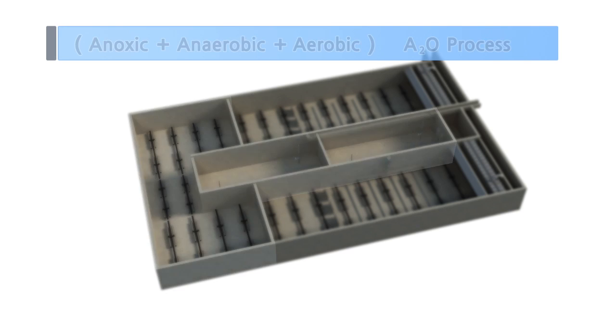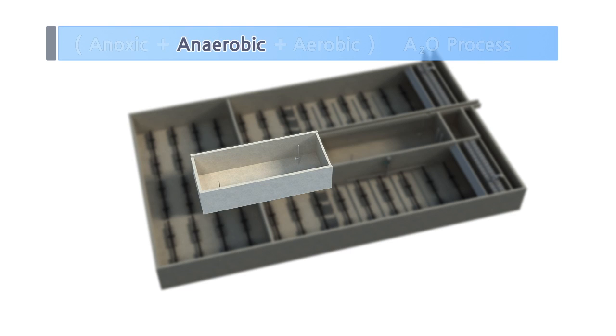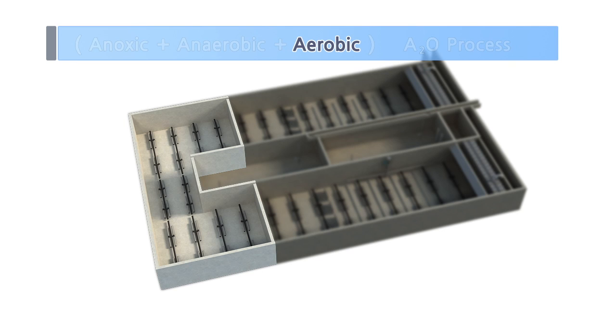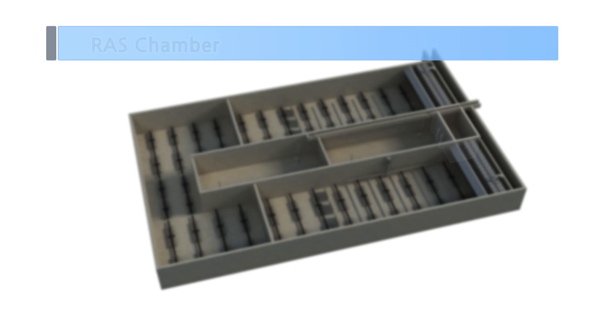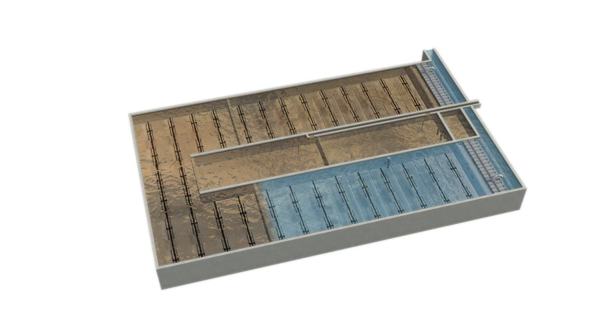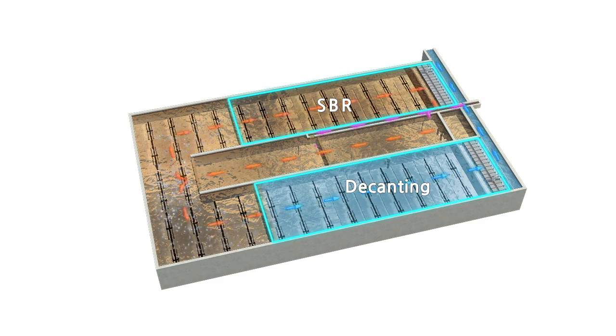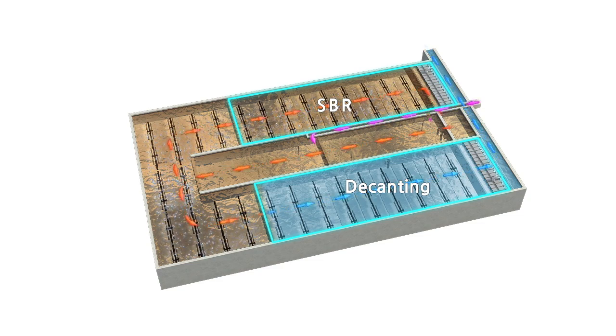This system is composed of an A2O process with three cells: anoxic, anaerobic, and aerobic, with continuous flow, together with two symmetrically arranged SBR cells. There is an ARS chamber located between the two SBR cells for the return of activated sludge. While one of the SBR cells functions as a settling cell to discharge treated water, the other SBR cell plays the role of a reactor by supplying air.